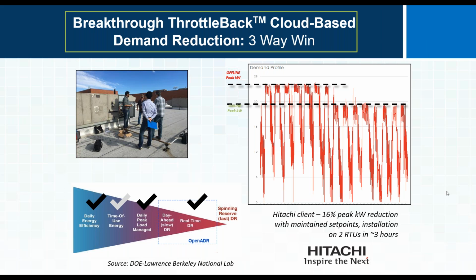This is one picture of our demand reduction technology in action — this is a Hitachi project. As an example of the speed of installation, this won't always be the case, but because we're a low voltage node-based solution, the gentleman who did the installation hadn't seen us or this system before 9 o'clock in the morning, and by 12 he had the nodes installed in 2 fairly large air conditioning units, one of which you can see behind him. We were able to deliver fault detection and monitoring for this client, as well as the 16% peak kW reduction that you see there.